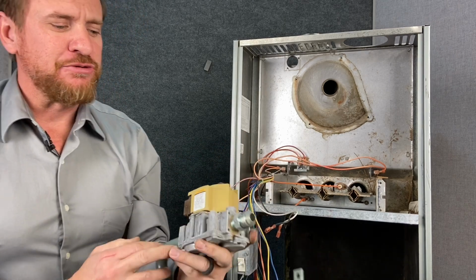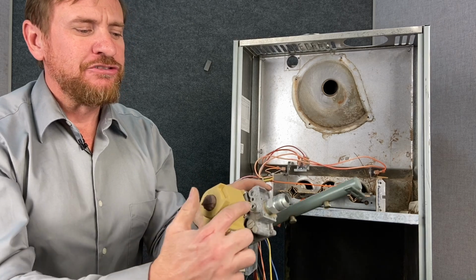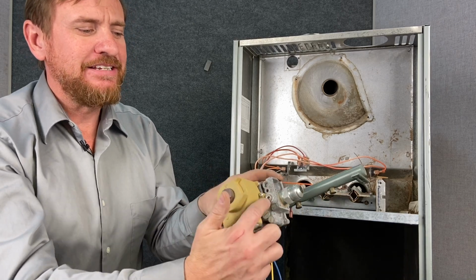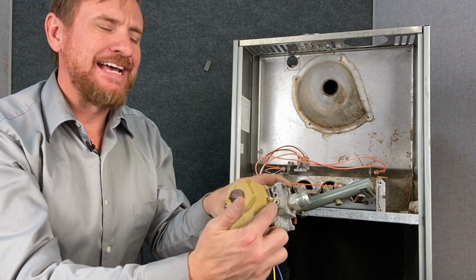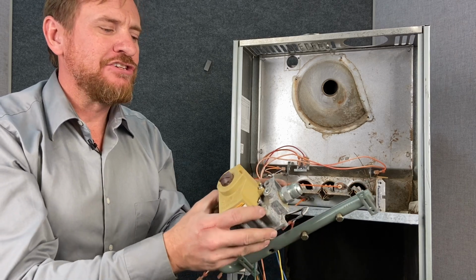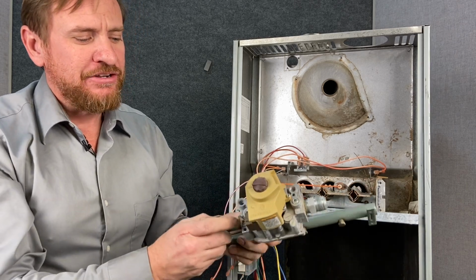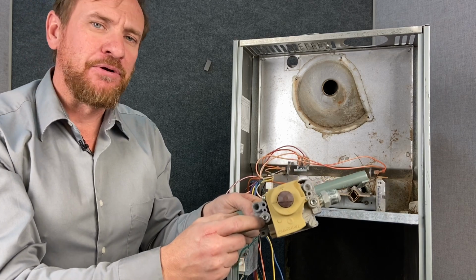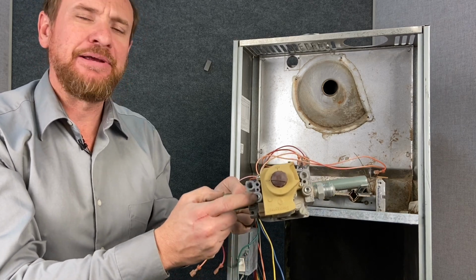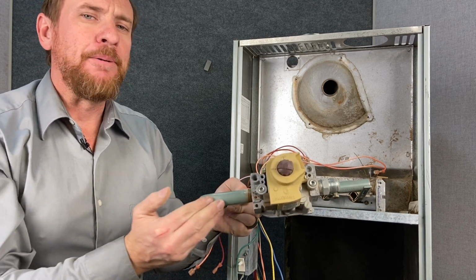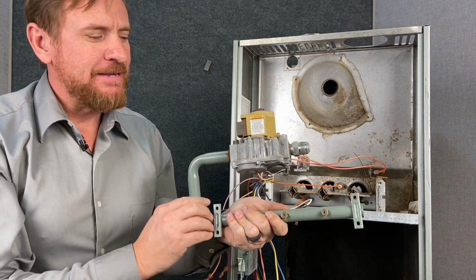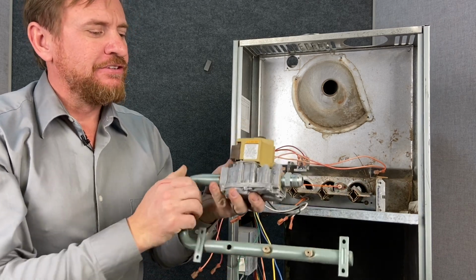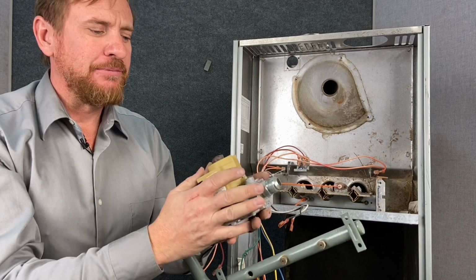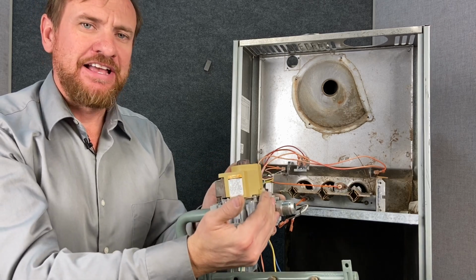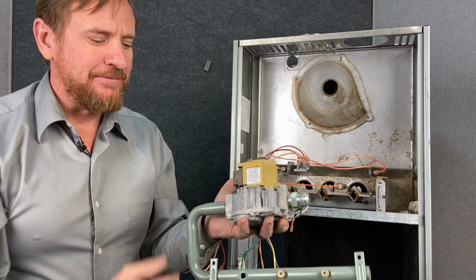There's 2 kinds of pressure we have: incoming gas pressure. So in this very port on the top it says in. We can take that port out, we put an adapter there, and we can check the inches of water column incoming pressure. And on the other side, it has the same exact port. We can put the same adapter on, and this is going to be our output pressure, or what we call manifold pressure. So we want a set amount of manifold pressure on this. So that's our combination gas valve, very simple component. We have to make sure we have gas available coming in and gas coming out as well.